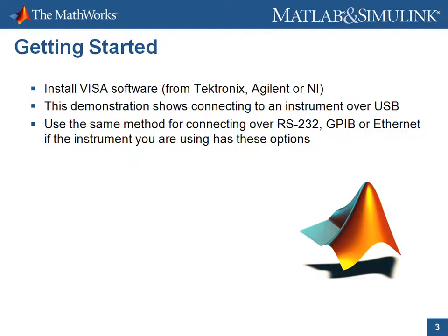Before we get started, it is important that you install the VISA software from either Tektronix, Agilent, or National Instruments. This demonstration will show how to connect to the oscilloscope over a USB cable. However, you can use the same method to connect over GPIB, Ethernet, or serial interfaces if your instrument has those options. Okay, let's jump into MATLAB.